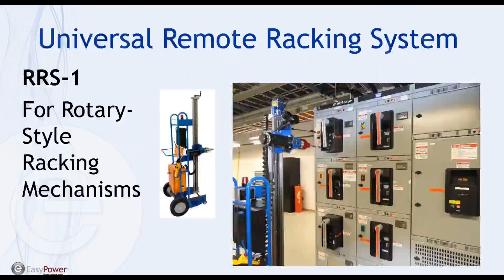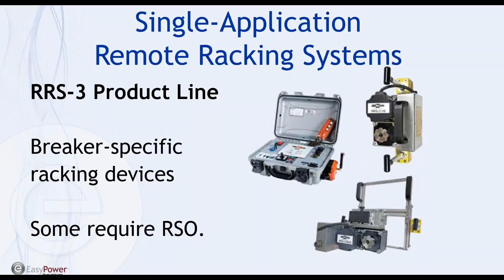The next application is our RRS3 product line, remote racking systems designed for specific breakers. For example, you may have a Magnum DS circuit breaker, and maybe that's mostly what you've got in your facility. We can offer, for a lower price than the universal device, a specific racking mechanism for that Magnum DS. Pretty lightweight, it attaches like our remote switching solutions with the twist of the magnets, and operates using an RSO, or control box, similar to what you saw with the switching devices. You can have a central RSO and then a few different individual racking mechanisms for your lineup at your plant or facility.